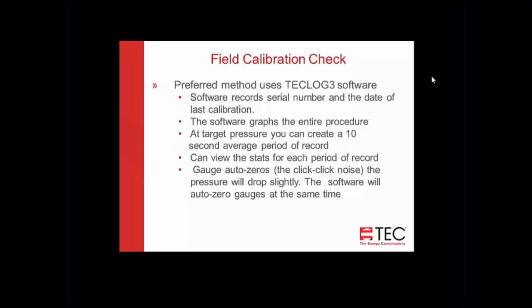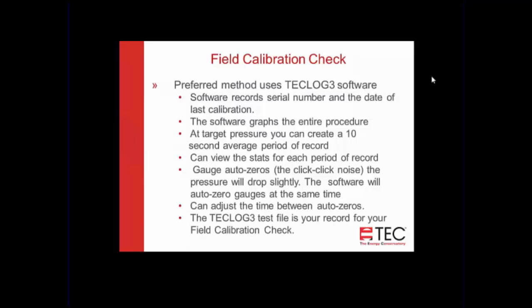But you can set the auto zero period to 1 minute in the software, and that gives you a chance to get your pressure set before the gauge auto zeros. And that provides your record. That TECLOG file is your record, and so you don't need a paper trail. You'll have that documentation that's rock solid.